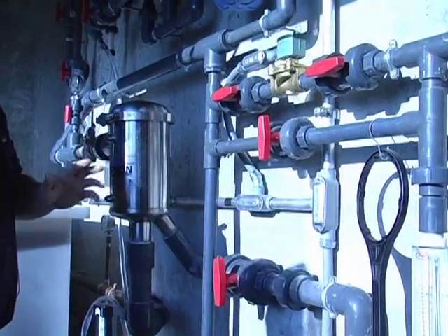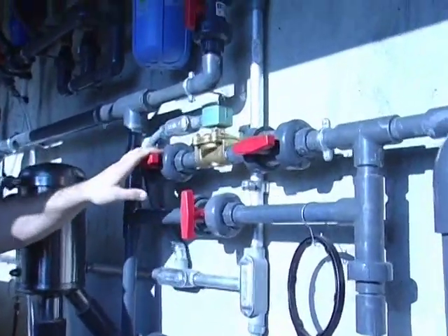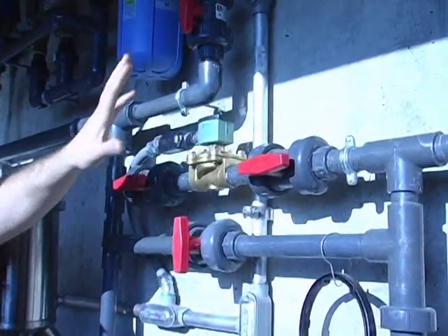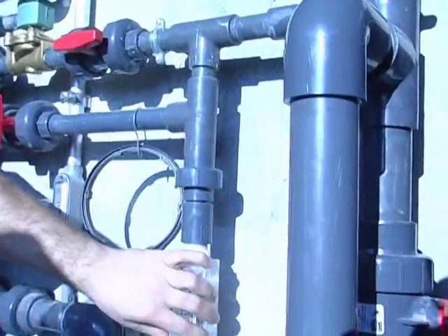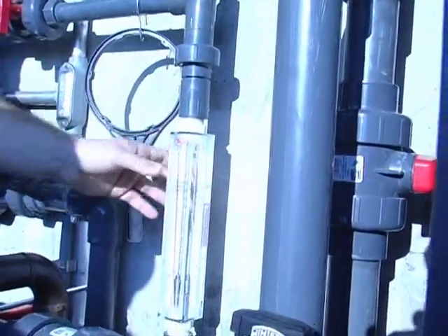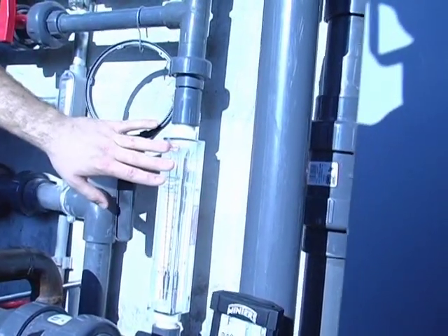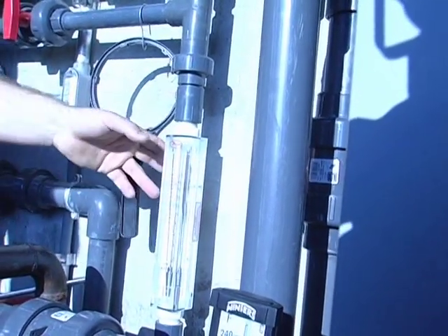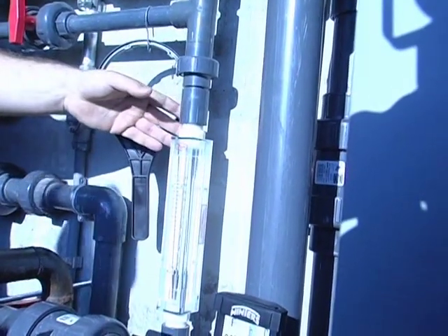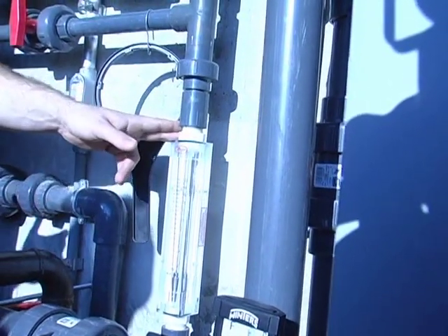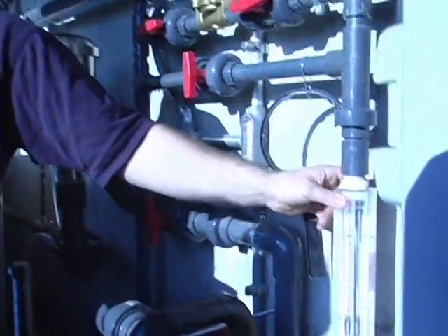So you have a solenoid valve here, and some other piping runs here where you can bypass the solenoid into this flow meter where you can monitor your flow rate. Again, with that flow rate you can adjust the amount of times daily you have to blow down or reintroduce fresh water to your humidification chamber to reach your desirable pH in your recirculation sump, which we'll take a look at over here.